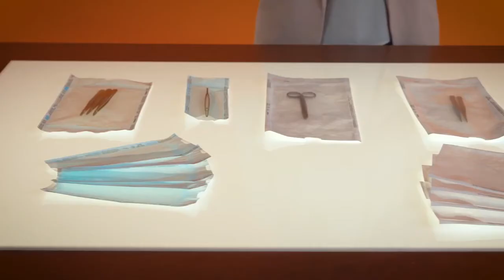Flat bags. If we choose this format, firstly, we open the cardboard box that contains the bags, which are protected by an interior plastic bag. The product to be sterilized is introduced into the bag and sealed along the open area with a sealing machine. As you can see, the upper area is already sealed.